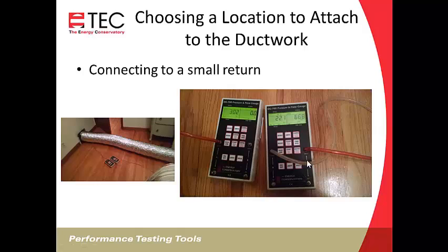We've got open fan, and we're only able to get, and this is CFM at 25, we're only able to get the system up to 22 pascals. So it's extrapolating whatever number we have up to 668. And if we're connected to a large return, a central return, or the air handler, we should be able to get 1350 CFM. Well, actually, because we're using the flex duct, we should still be able to get 1,000 CFM through that system, but we're only able to get somewhere around 600. And the reason for that is we've got a back pressure at over 300 pascals.